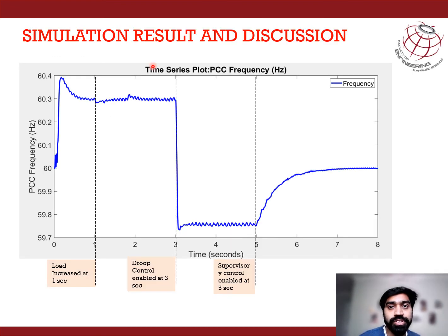So this is the simulation result of frequency deviation when we have changed the load at 1 second. And as you can see from this figure, droop control is enabled at 3 seconds. So frequency dropped, and at 5 seconds the supervisory controller was activated, and the system is trying to stabilize the frequency again at 60 Hertz. So this simulation result shows the frequency is within the range of droop set points, which are 60.3 Hertz and 59.7 Hertz.